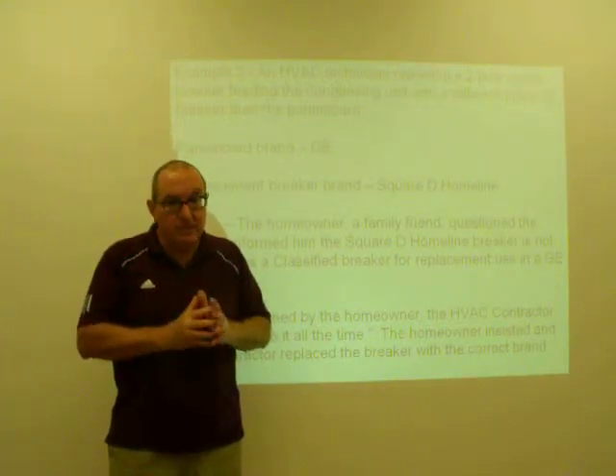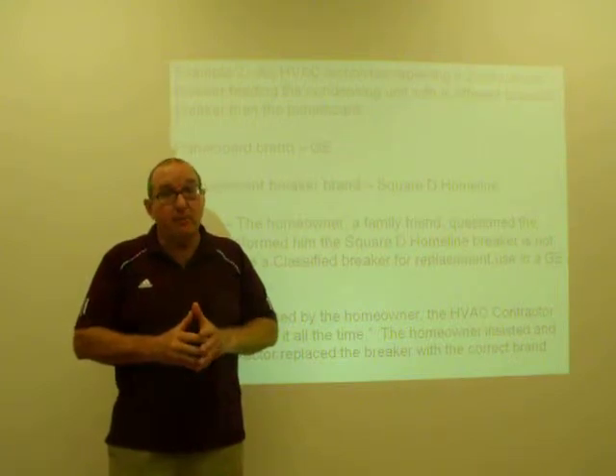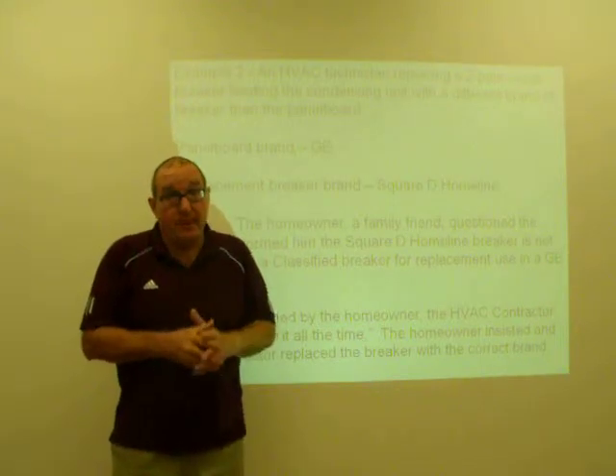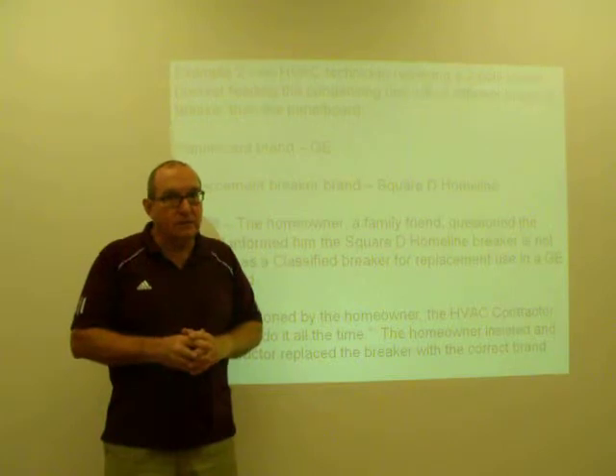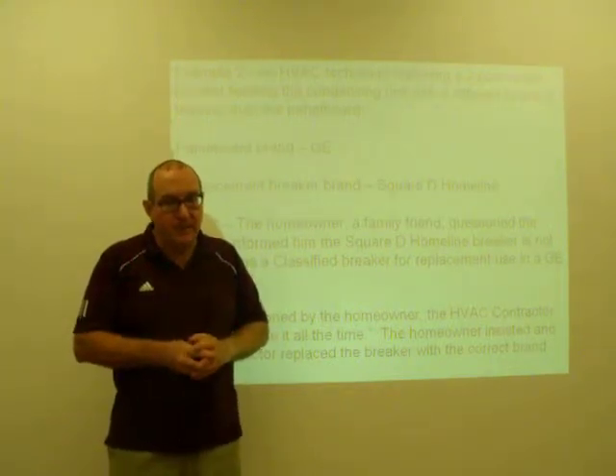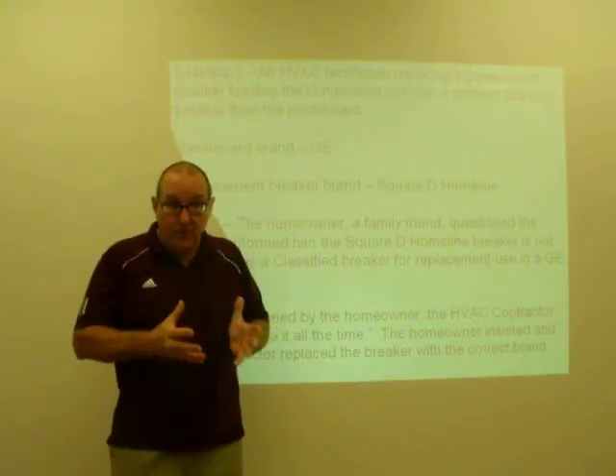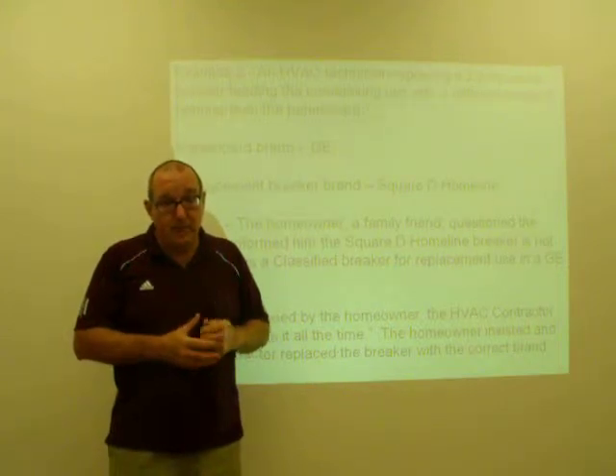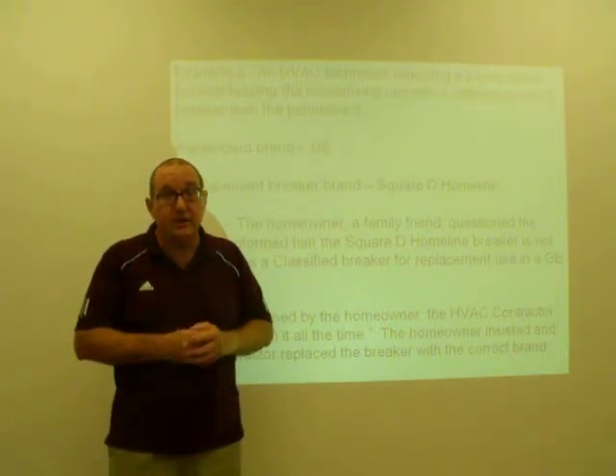I did a little bit of research to make sure I wasn't lying to him, and I told him, I could find no evidence that a Square D Homeline breaker was UL listed for use as a replacement breaker in a GE or anybody else's panel board for that matter. The homeowner called the contractor as a result of our conversation and explained the situation to him, and the contractor told him, well, we do it all the time. The homeowner was going to have me come replace the breaker at additional expense. And he was able to get the air conditioning contractor to replace the breaker with the proper GE breaker at the contractor's expense.